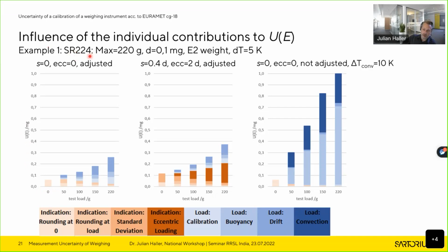Now let's start with a, let's say, very common example, a typical laboratory balance with a maximum of 220 grams and a scale interval of 0.1 milligram. We use E2 class weights for the calibration, and we say that the temperature variation at this installation site is 5 Kelvin. And now if you just consider the perfect calibration result, standard deviation is 0, eccentricity is 0, and the balance was adjusted directly before the calibration. You see you have different contributions contributing to the uncertainty. For higher test loads, the reference weights' uncertainty contribution gets more important. But if you assume more realistic calibration results, so you have a standard deviation of approximately half a digit and an eccentricity deviation of 2 digits, you see that already these respective contributions, the red or brown ones, get more important.